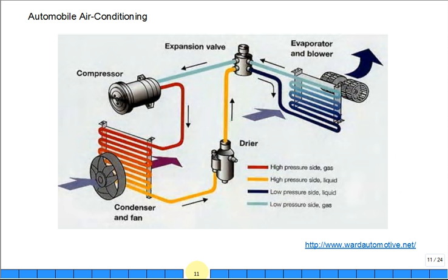So here's another illustration. It just confirms it. They color code it. I like the color coding. So it comes out high pressure liquid, goes through the filter dryer, goes up to this expansion control device. And I'm going to pass one around. If you took Thermo 1 with me, maybe I passed this around. I like to pass it around. It has a passage in the block that has a liquid going this way on the bottom. And on the top, what does it have coming out of the evaporator? This right here, color-coded low-pressure gas or vapor. And so it's low-pressure vapor going through.